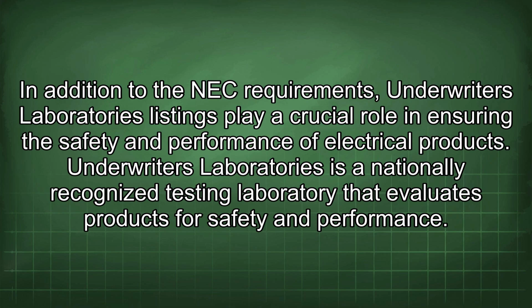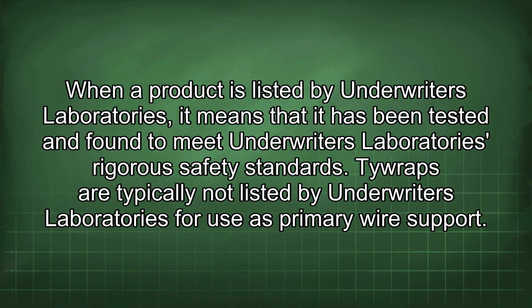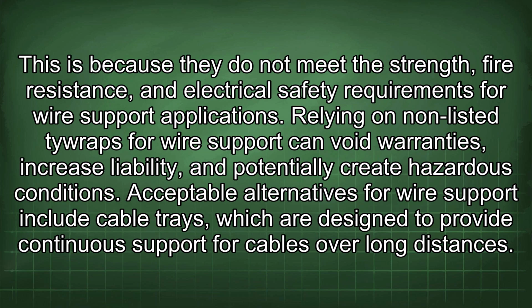In addition to the NEC requirements, Underwriters Laboratories listings play a crucial role in ensuring the safety and performance of electrical products. Underwriters Laboratories is a nationally recognized testing laboratory that evaluates products for safety and performance. When a product is listed by Underwriters Laboratories, it means that it has been tested and found to meet their rigorous safety standards. Tywraps are typically not listed by Underwriters Laboratories for use as primary wire support. This is because they do not meet the strength, fire resistance, and electrical safety requirements for wire support applications. Relying on unlisted Tywraps for wire support can void warranties, increase liability, and potentially create hazardous conditions.